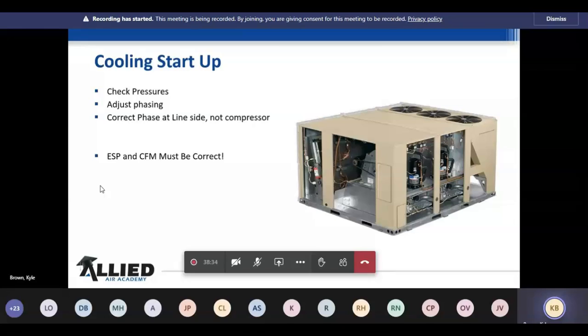So back to checking pressures, adjusting phasing, and things of that nature. You're going to want to check your pressures. You're going to want to make sure your compressors are running the right direction too. For those of us who ever heard a 3-phase scroll compressor run backwards, it is a very distinct noise. You can tell it. For some folks who haven't been in the field as long, and as we're trying to teach and get them up to speed, they need to look at the gauges. You need to check your gauges anyway, but your pressures will show it as well too.